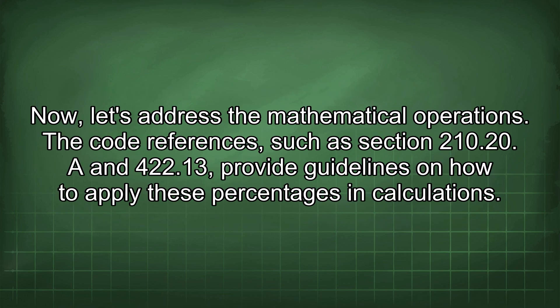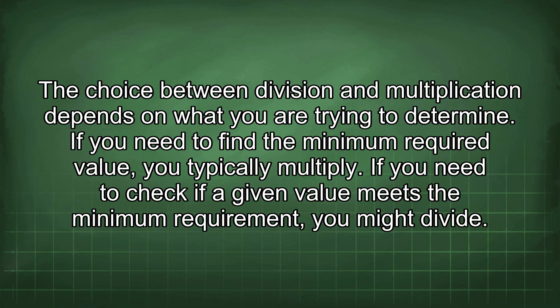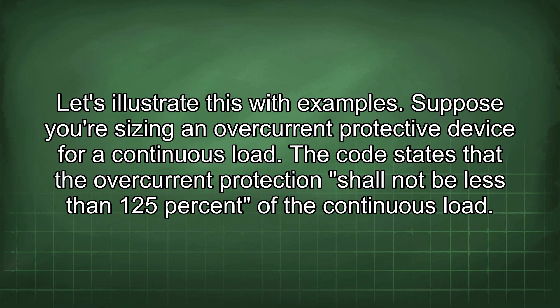Now let's address the mathematical operations. Code references such as section 210.20 and 422.13 provide guidelines on how to apply these percentages in calculations. The choice between division and multiplication depends on what you are trying to determine. If you need to find the minimum required value, you typically multiply. If you need to check if a given value meets the minimum requirement, you might divide.